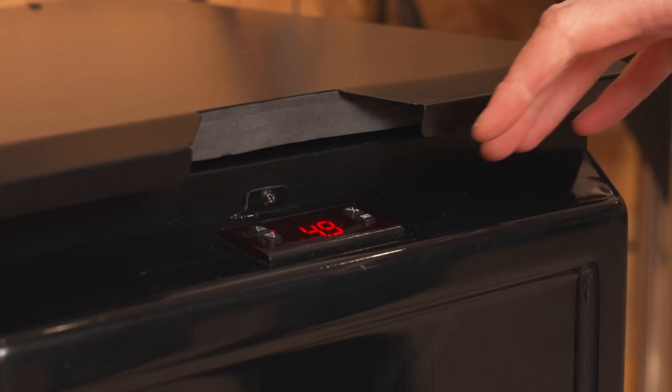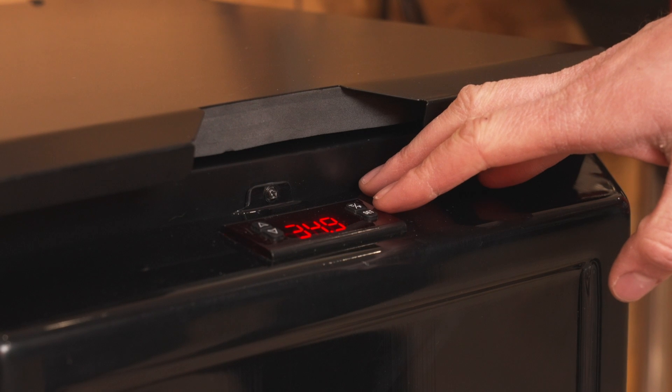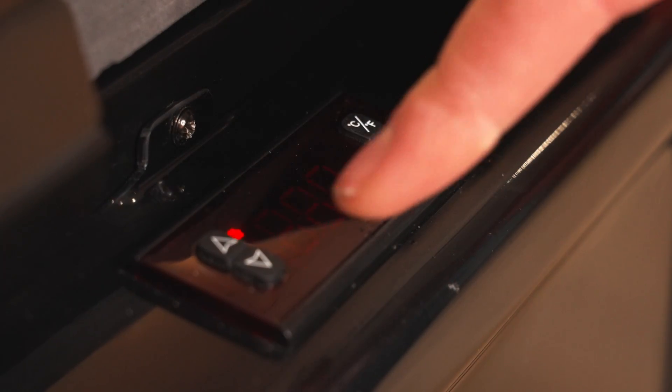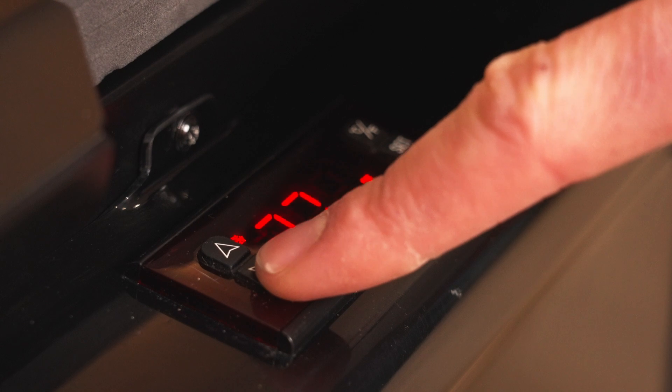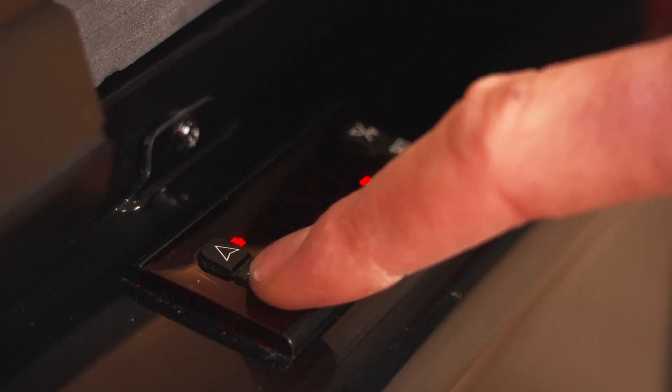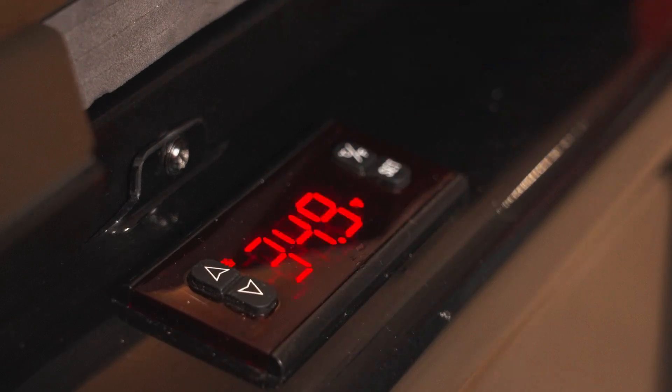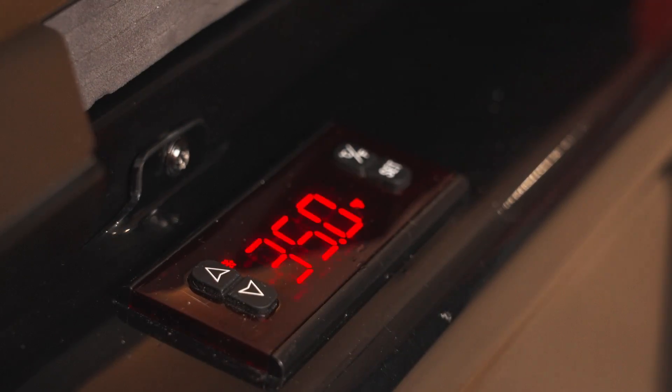To set the reservoir temperature, press the Set button on the control panel. The temperature setting should start blinking. Use the arrow keys to change the temperature up or down to your desired value. When you're ready, press the Set button again to lock in the set temperature.